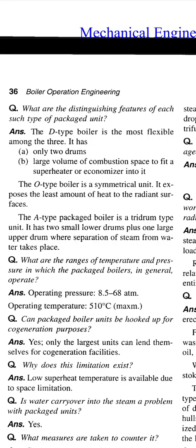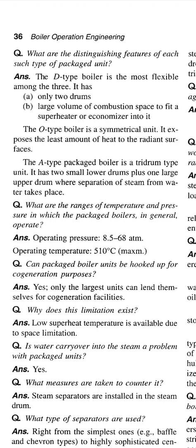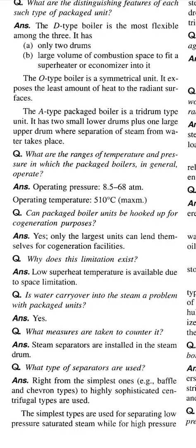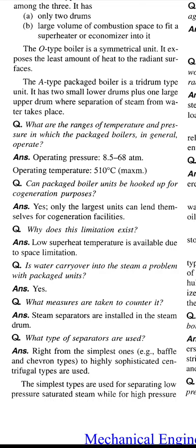The next question: what are the ranges of temperature and pressure in which the packaged unit boiler in general operates? Answer: operating pressure 8.5 to 68 atmospheres. Operating temperature is 510 degrees Celsius maximum. The next question: can packaged boiler units be hooked up for cogeneration purpose? Yes, only the largest units can lend themselves for cogeneration facilities. Why do these limitations exist? Low superheat temperature is available due to space limitations.